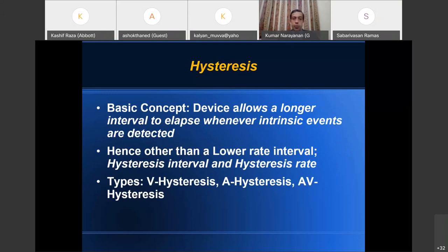So therefore, if you program hysteresis on, then you will have another interval in addition to the lower rate interval. And this will be the hysteresis interval. And corresponding to that, there will be a hysteresis rate. So we said that the lower rate interval is an inviolable principle of the pacemaker.